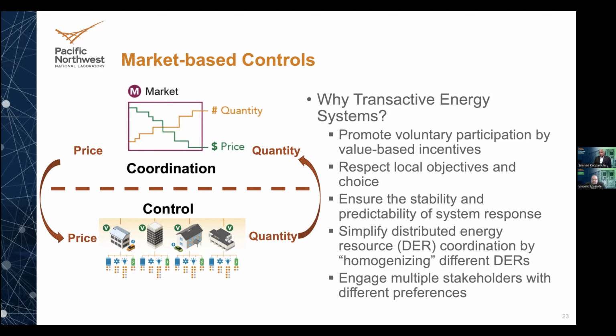Absolutely. The availability of the battery system is significantly different from even thermal storage or virtual storage. Virtual storage is only one way, you can reduce consumption but you can't generate anything. Thermal storage is the same, you can reduce peak consumption, whereas battery is bidirectional, you can charge and discharge and provide a number of grid services very quickly. Thermal storage and virtual storage have latency that isn't conducive to some of the fast grid services.